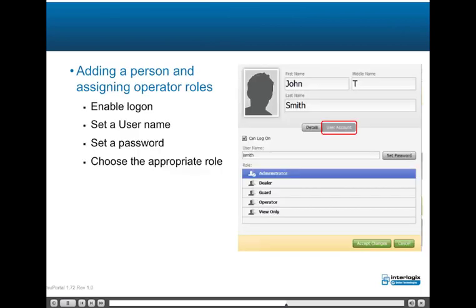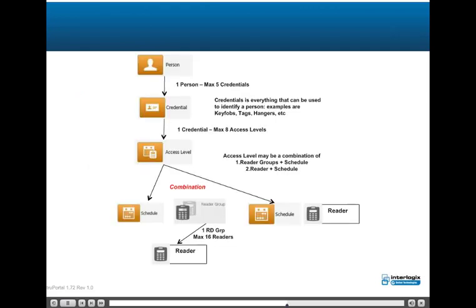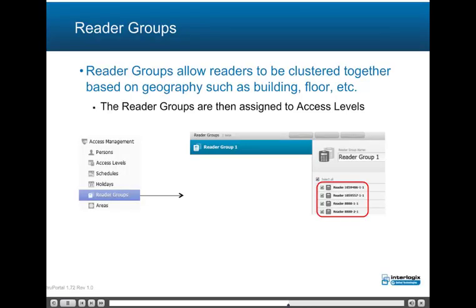Adding a person and creating a user account consists of enabling the user account (can log on), setting a user name, setting a password, and choosing the appropriate role which controls permissions. One person may have a maximum of five credentials. A credential is used to identify a person accessing a reader — examples include cards, key fobs, tags, and hangers. One credential may have a maximum of eight access levels; an access level may be a combination of a reader group and a schedule, or a reader and a schedule. Reader groups allow readers to be clustered together based on geography such as building, floor, etc., and the reader groups may then be assigned to access levels.